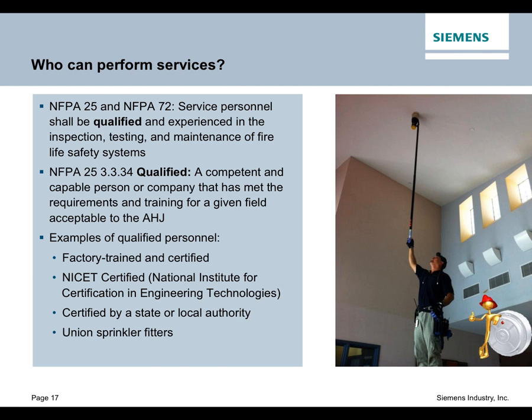So let's touch on the important statement about who can perform the services. The codes themselves, 25 and 72, state that the service personnel shall be qualified and experienced in the area that they're inspecting, testing, and maintaining. Therefore, a person who is experienced in fire sprinklers can do fire sprinklers, but maybe not necessarily fire alarms unless he's also been cross-trained. And you can see here in 25, they're giving you a definition of qualified, competent, and capable person.